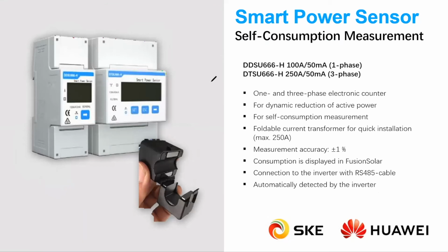We can also provide power meters. For commercial applications, we have the three-phase DTSU666H, with 250 amps maximum output current for all of the inverters. It has a high measurement accuracy. You can monitor self-consumption and import of power on our monitoring platform if you have this power meter connected. You can connect the power meter to the inverter by using an RS485 cable. For easier commissioning, these power meters are automatically recognized by the inverter and added during the commissioning phase.